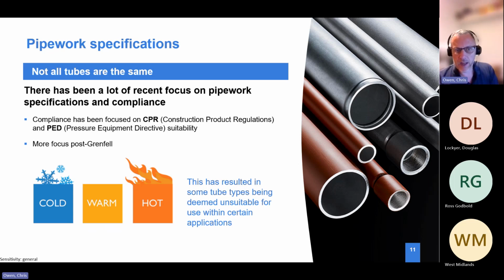The PED can apply at pressures above 0.5 bar. There are some restrictions if you don't go over a certain pipe diameter, but if you connect to something 8-inch, 200 nominal bore and above, the PED actually pulls the smaller diameters in, because you take it as a system. So the PED is quite important.